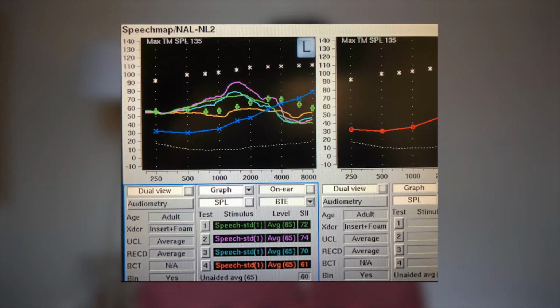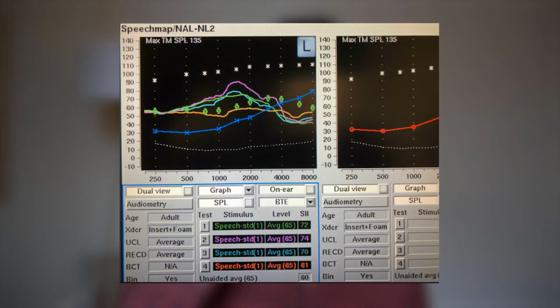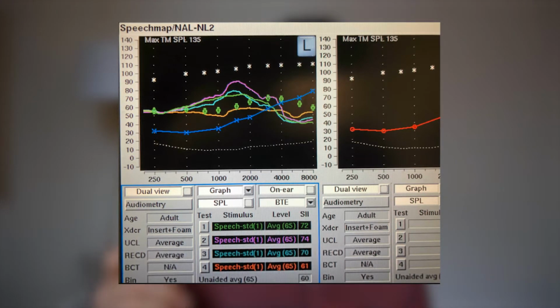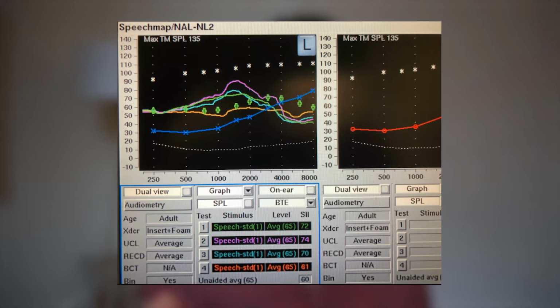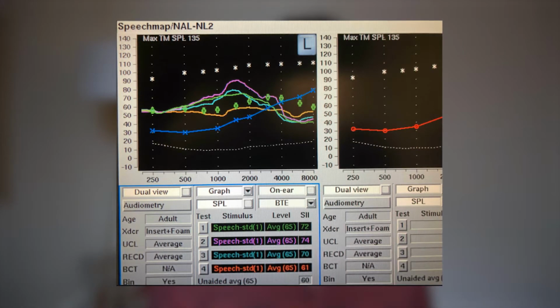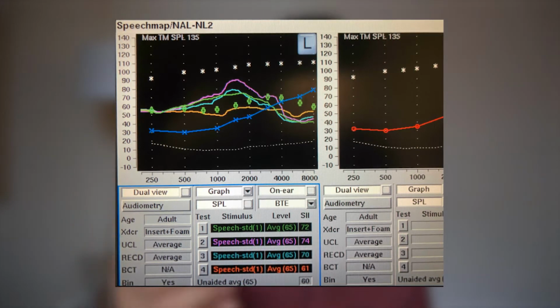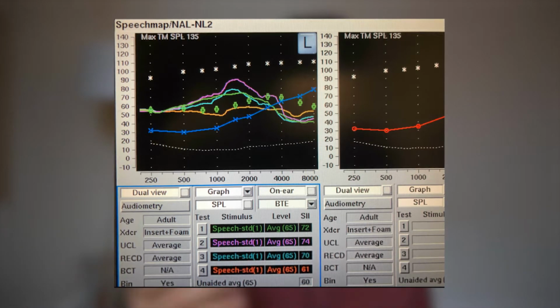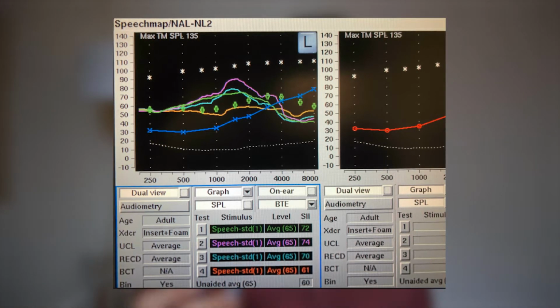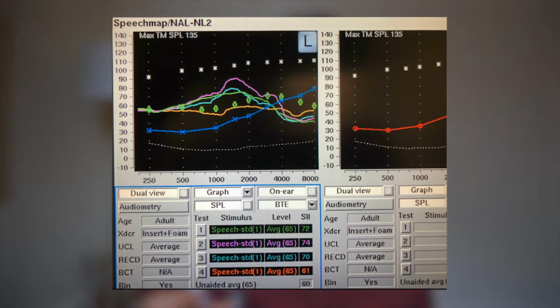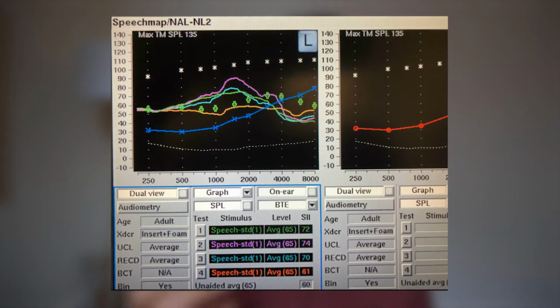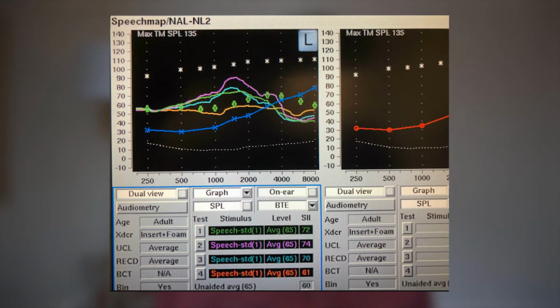The orange line at the very bottom is actually the recording of sound in my ear canal with nothing in it. So that's our reference point here. And then we see these 3 different levels of volume control for how the hearing aid works. As you can see, for each of the volume levels, it's far over those green targets. That means this is too loud, and if you put this in your ear, it's not going to sound pretty.